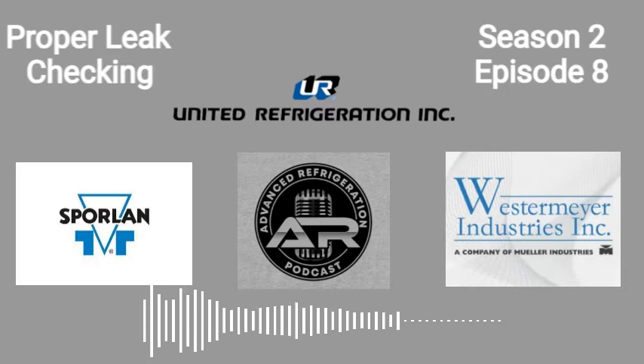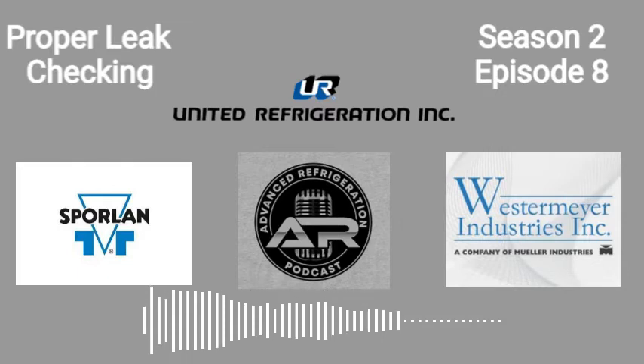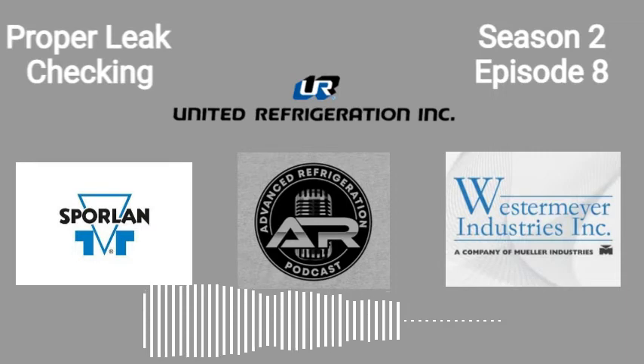So when you block the airflow, it heats the diode up, and then it makes it look like it's a leak. So just don't shove it in there. And the same with the H10, don't suck up moisture in that thing. It's very sensitive to that. So you want to keep it just above the Armaflex where you slit it.